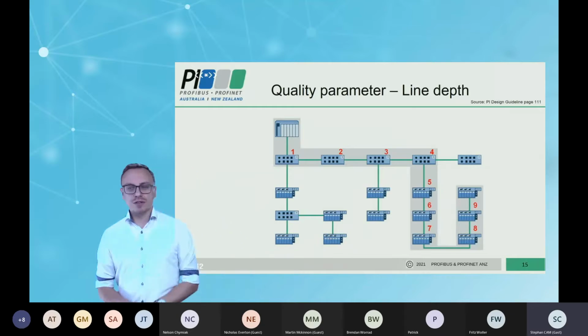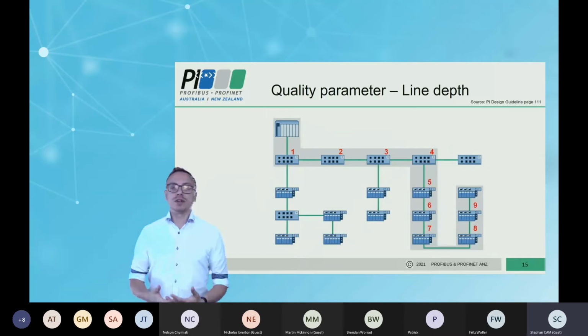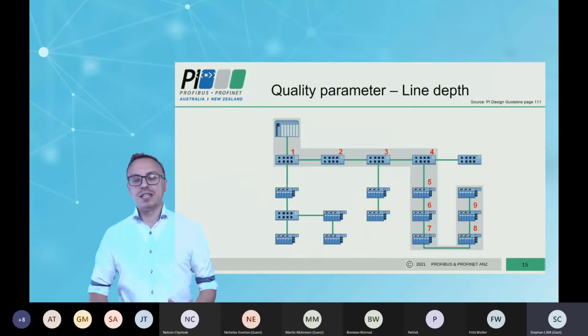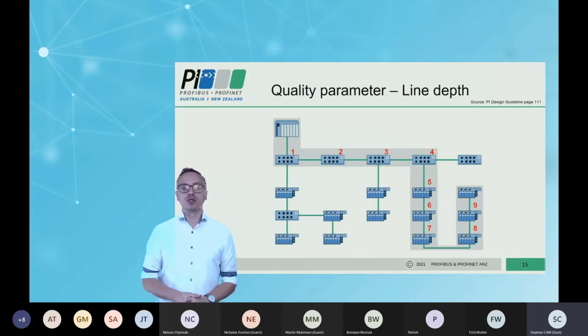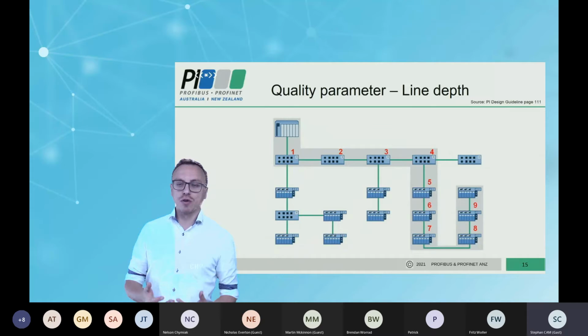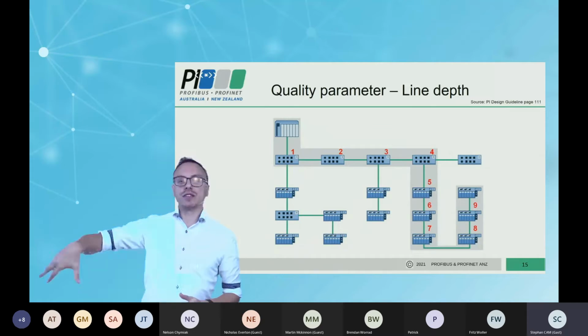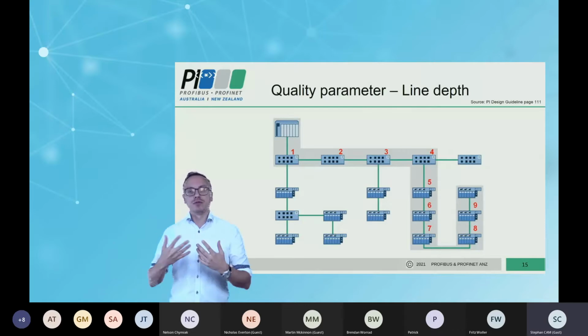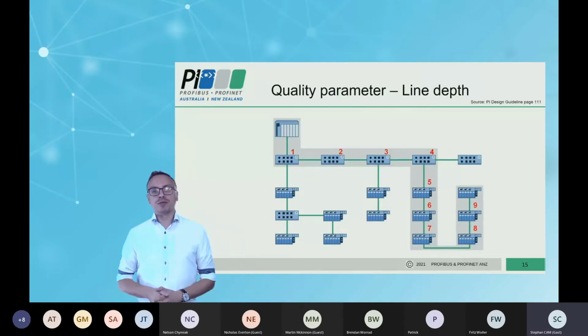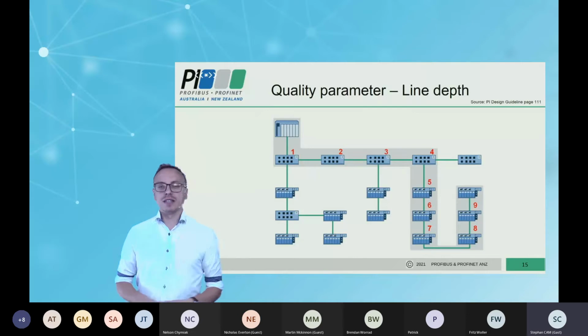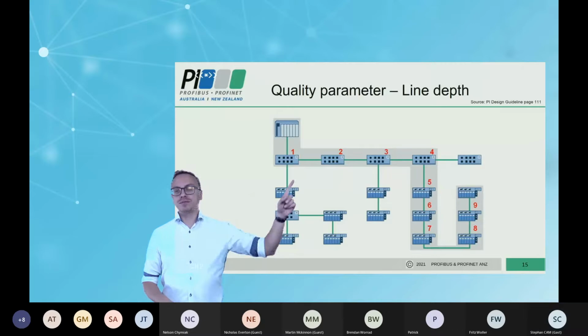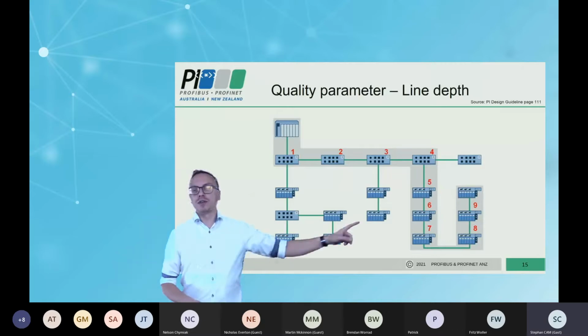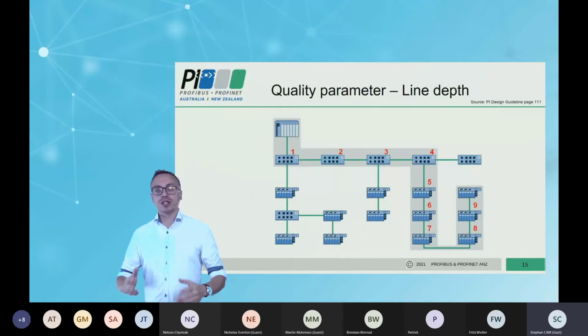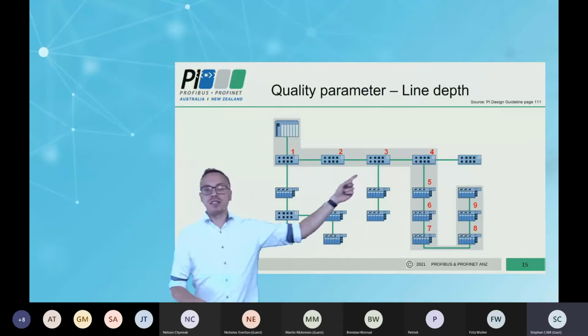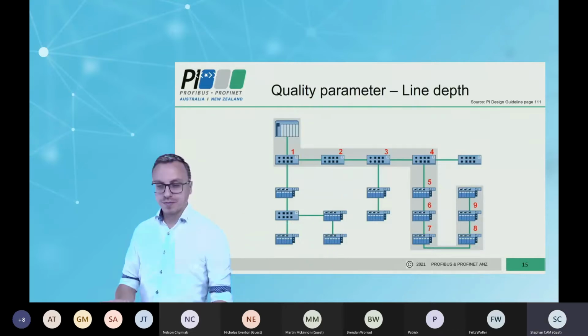Why is it important to know? As I said, each device sends information to the PLC. That means each device creates net load. Is your net load too high in a line? You get issues, or better to say, the device gets overloaded, and it's possible that this device will discard frames. And because of this discarding of frames, you get a stop of your plant. So, for example, if your PLC runs with 1 millisecond, you can handle a line depth of up to 7. If you have a line depth of, for example, 9, you have to change the update time of these devices in this line to 2 milliseconds.